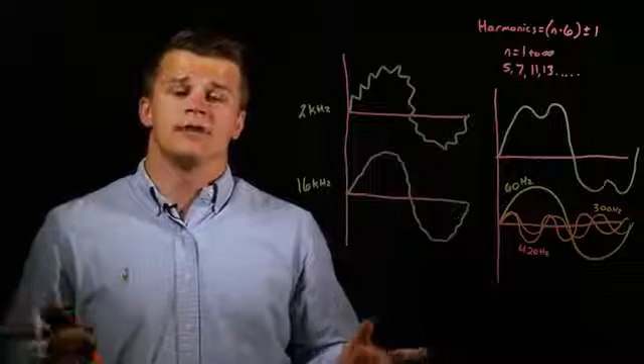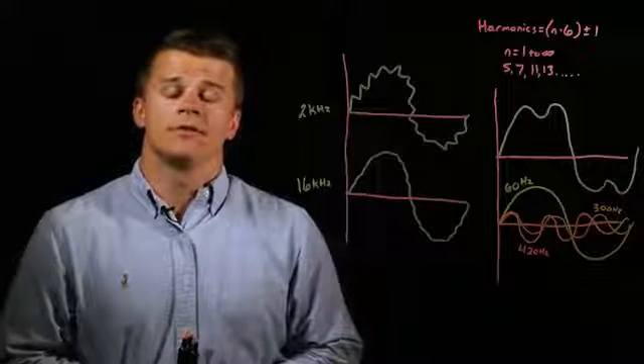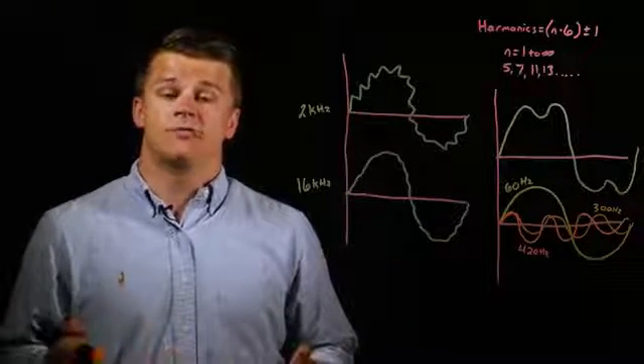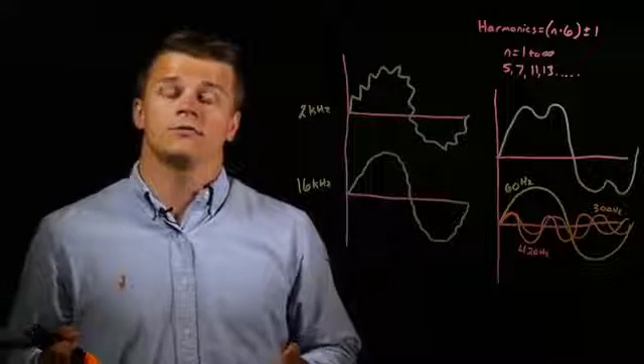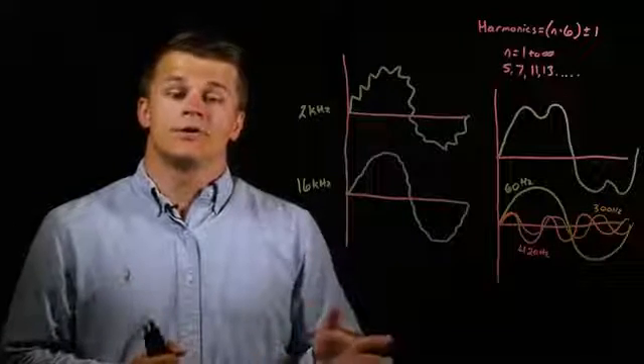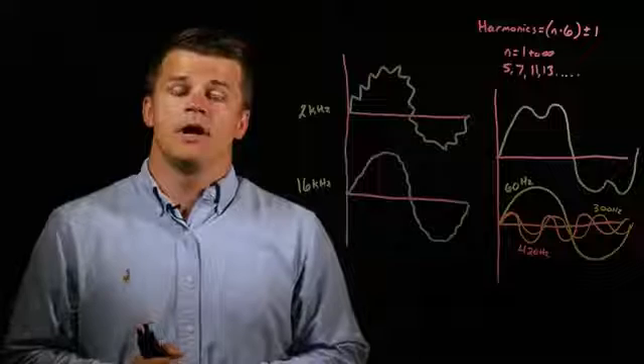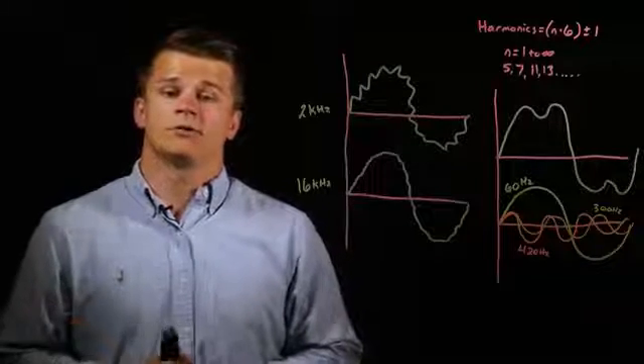There are some downsides in increasing the switching frequency. The biggest is that it increases heating in the drive because the IGBTs are switching on and off so rapidly. It can also increase EMI noise in the system and cause you to derate the output current to the motor.